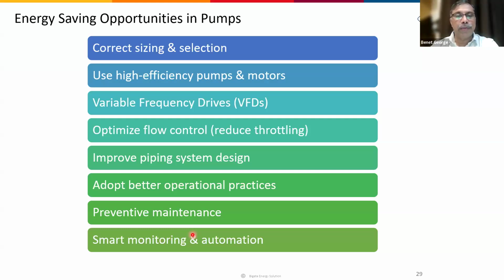Then a variable frequency drive can be used based on the application. If it is a variable flow requirement, you can use a variable frequency drive. Always avoid the... Then improve the piping design. You can check whether the shortest distance is possible, the sizing of the pipe, and how many bends there are. All of this can improve the overall efficiency of the system.